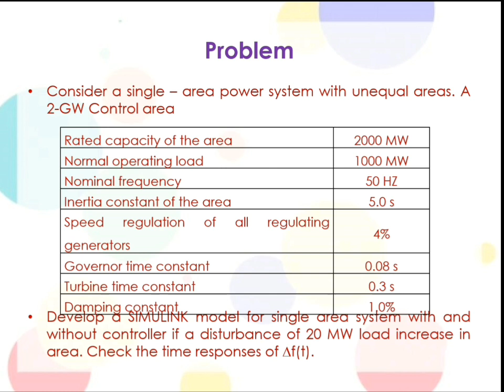First, we have to determine the load damping constant B, which is equal to dou PD divided by dou F. Here the PD value, that is the normal operating load, is 1000 megawatt and the frequency is 50 Hz. We are assuming that for a 1% change in the load, there is a 1% change in frequency. So B is determined as 1 by 100 into 1000 divided by 1 by 100 into 50, which is equal to 20 megawatt per hertz. Here we have to determine it in per unit megawatt per hertz, so the value is divided by the rated capacity of the area PR, which is 2000. So 20 divided by 2000 is equal to 0.01 per unit megawatt per hertz.